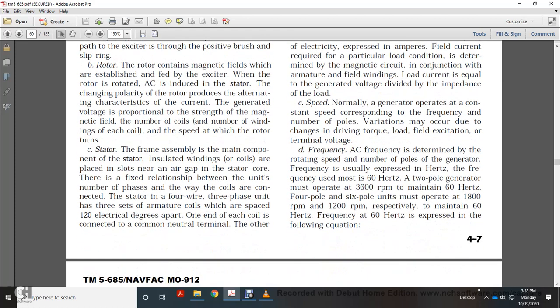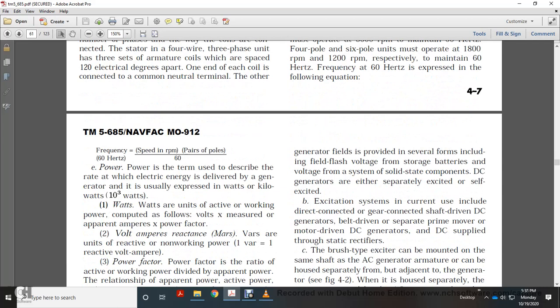Field excitation, terminal voltage. AC frequency is determined by the rotating speed and the number of poles that generate the frequency, expressed in hertz. For example, a two-pole generator must operate at 3600 RPM to maintain 60 hertz. Four-pole and six-pole units must operate at 1800 RPM and 1200 RPM, respectively, to maintain 60 Hz. Frequency of 60 Hz is expressed in the following equation: frequency equals speed in RPM times the number of pairs of poles over 60.